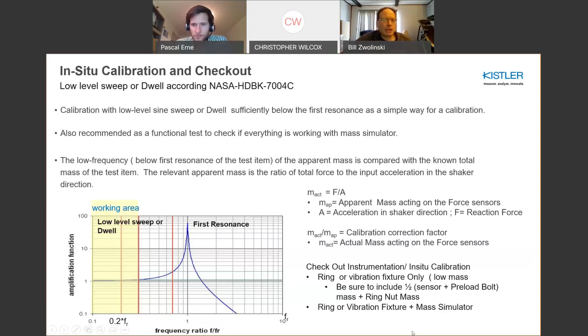One call I got recently was from an application where they were just doing the vibration fixture, so there's fairly low mass acting upon the sensor, and the engineer saw about a 16% deviation between the apparent mass and the actual mass. What we found out was that we didn't add half the sensor mass and the preload bolt mass in the total mass calculation. Once we did that, the apparent mass and actual mass were fairly close, within say 1%, and the calibration was properly done in that regard. So always take care when you're doing these in situ calibrations to account for all your mass sources acting, so you get the best in situ calibration.